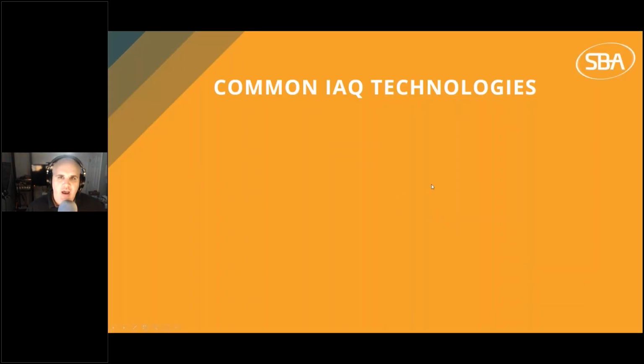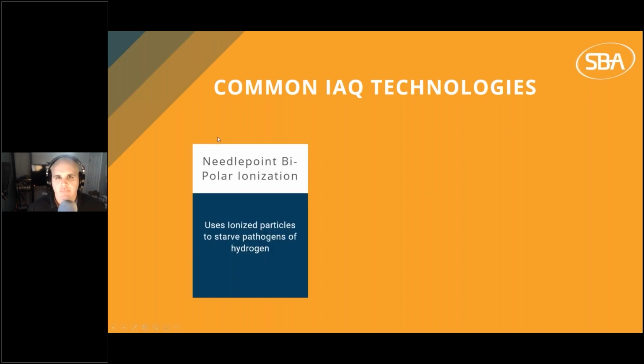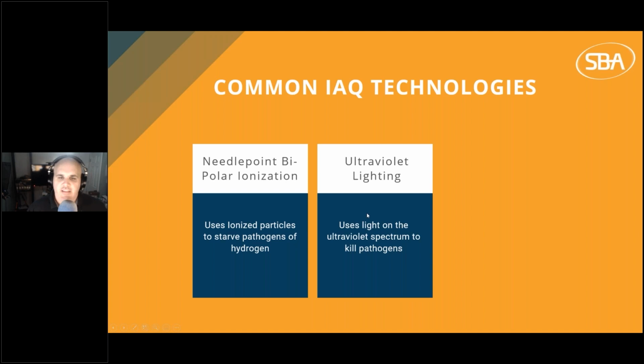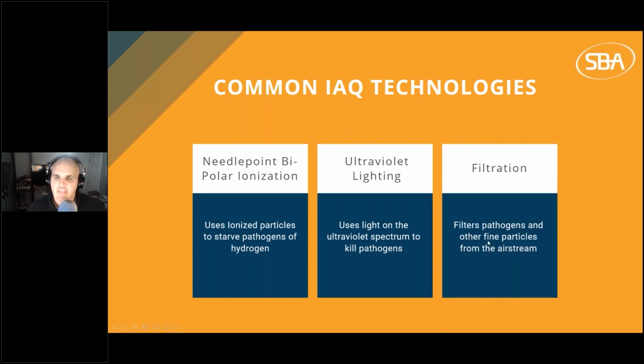All right, common IAQ technologies. First, needlepoint bipolar ionization. I'm sure a lot of you have heard about this. NPBI. So it's kind of a mouthful. Basically, in a nutshell, it's going to ionize some particles, and these are going to attach themselves to pathogens and starve the pathogens of hydrogen. Then we have ultraviolet lighting, and this is going to use light on the ultraviolet spectrum to kill pathogens. And then we have filtration, and this is going to filter pathogens and other fine particles, PM 2.5 and PM 10, from the airstream.